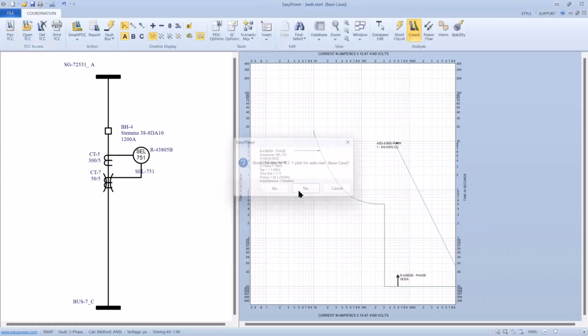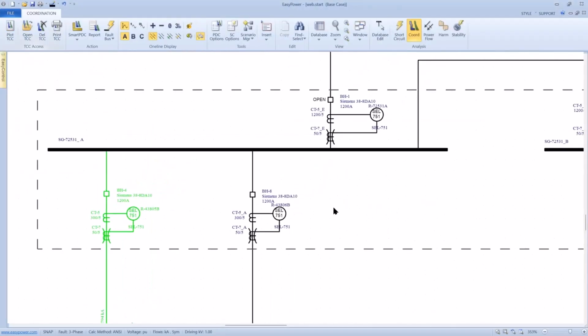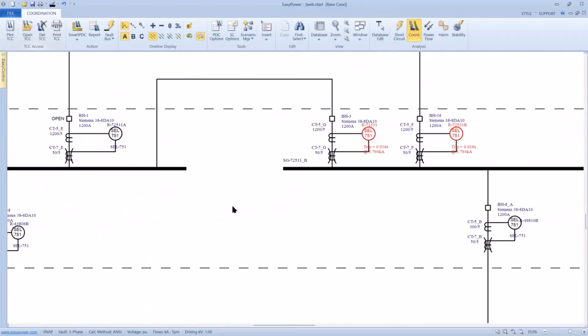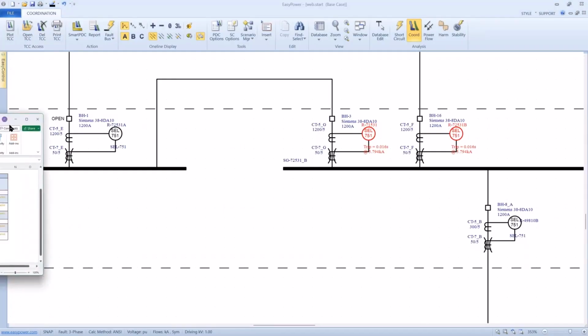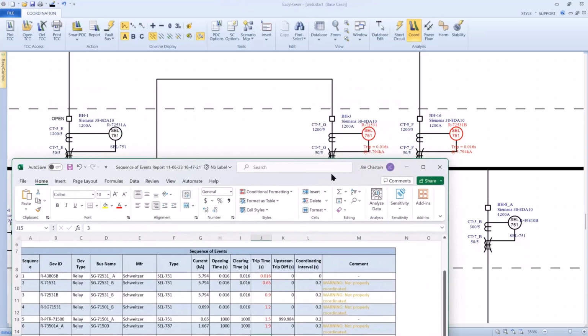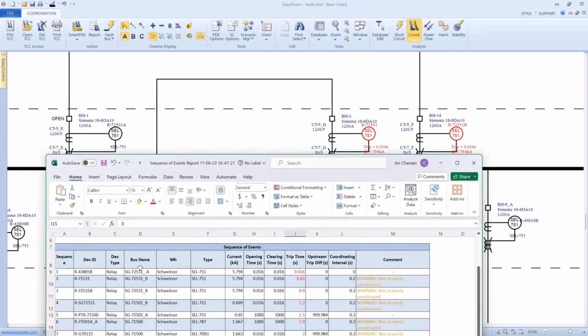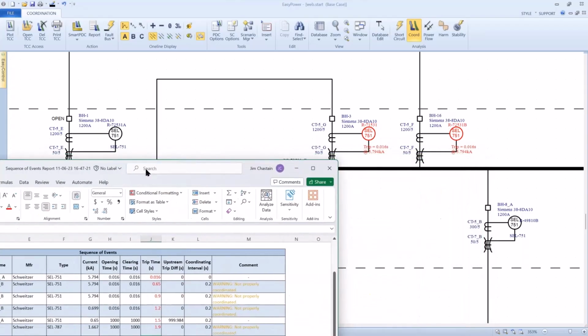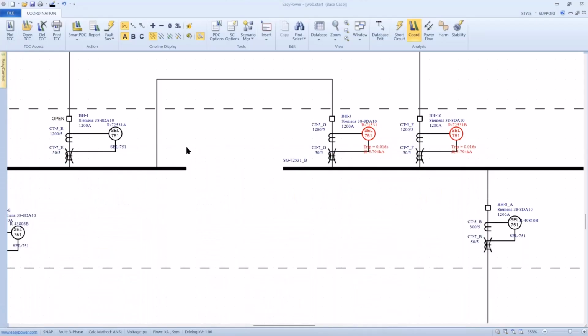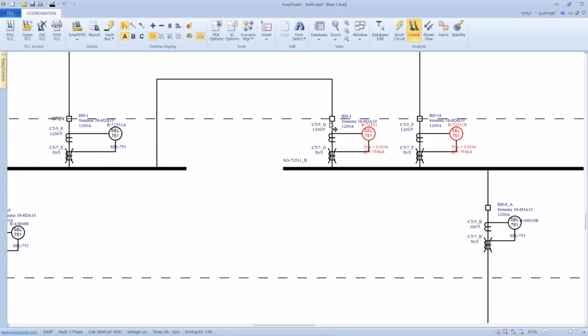All right, I'm going to close this, not save it because I don't want to clutter up my directory. And as I scroll up, I see the next relay in line is this one. And if I go back and look at my printout, relay 71531, I want to be set up for about a 650 millisecond trip at the interrupt rating. Oh, that's another thing I wanted to point out. So let's plot this.